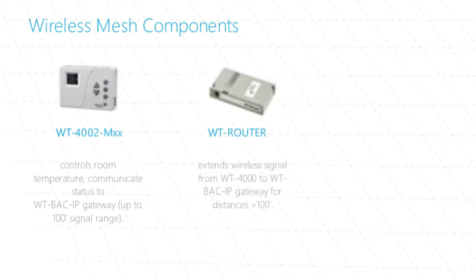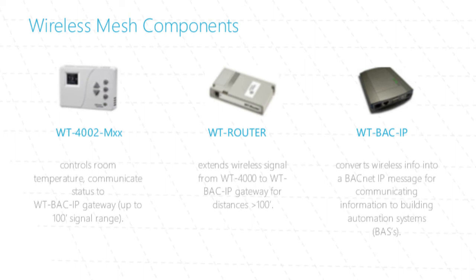The wireless mesh consists of three components. WT-4000 series thermostats control the room temperature and send their status to the WT-BAC-IP gateway; each device has a signal range of up to 100 feet. The WT router extends the wireless signal from the thermostats to the WT-BAC-IP gateway. The WT-BAC-IP converts wireless data into a BACnet IP message for communicating information to building automation systems.